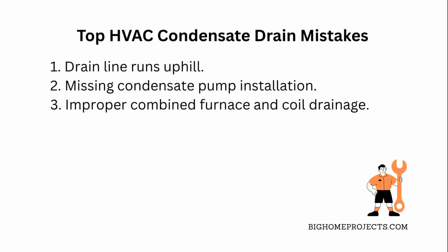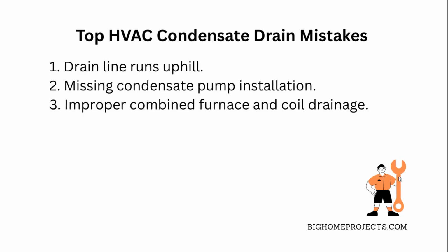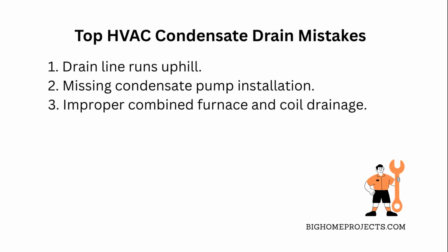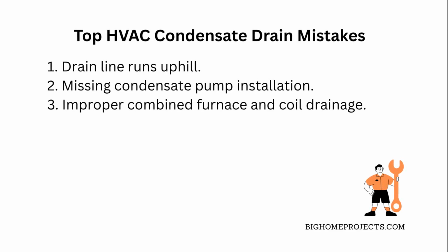Third, people often ignore separate drainage for condensing furnaces, which generate their own condensate. Combining lines without proper setup causes backups and mold. Always keep furnace and coil drainage distinct unless your system is designed for a combined line with proper traps and vents.